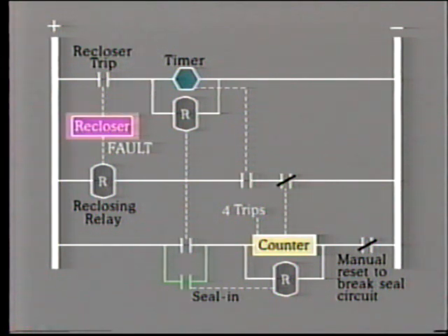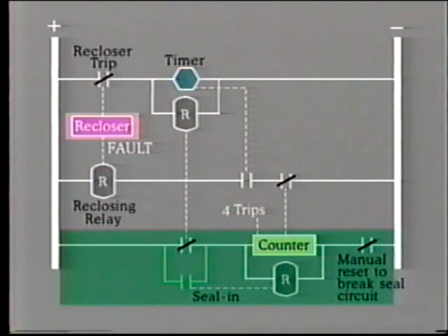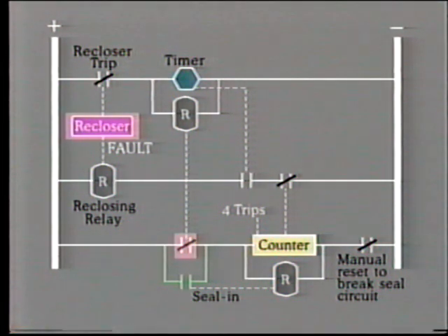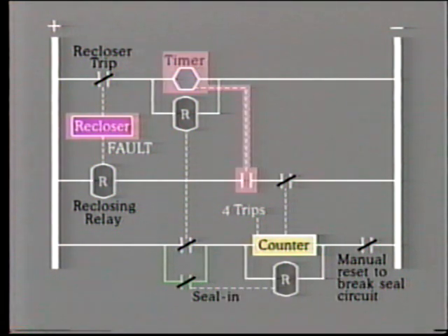When the recloser trips due to high overcurrent, this auxiliary contact closes and starts both the timer and the counter. The counter circuit is shown on the 3rd rung of this diagram. Note that once the counter contact is made, it is latched in by this seal-in contact. This is because we need it to keep counting through several reclosures and not reset each time. Now, when the timer times out, its contact closes, so energizing the reclosing relay. Note that the counter contacts are normally closed until it completes its preset count.